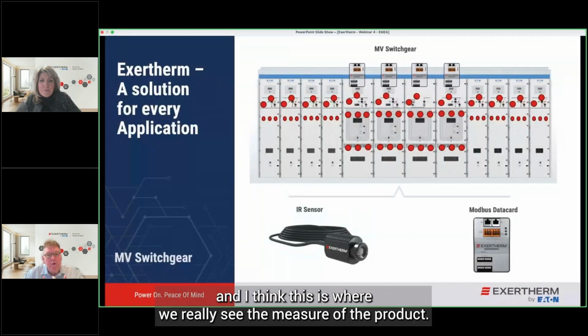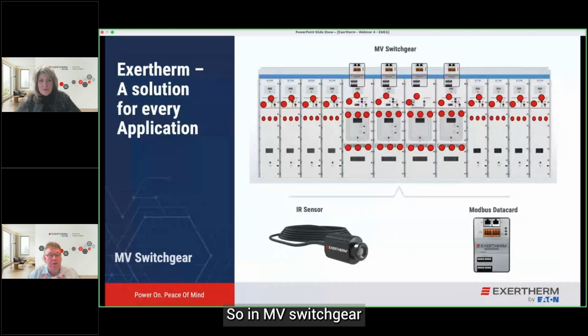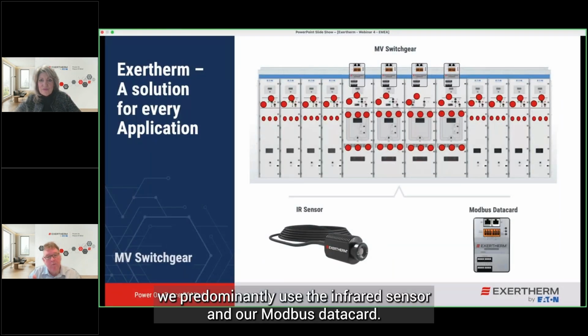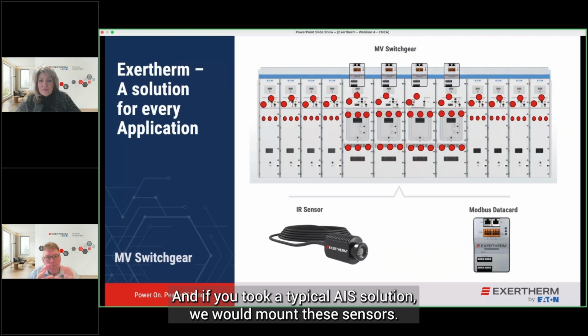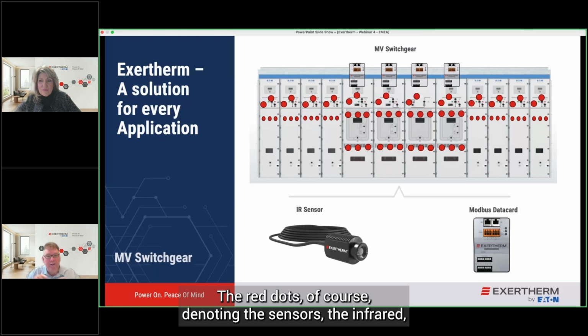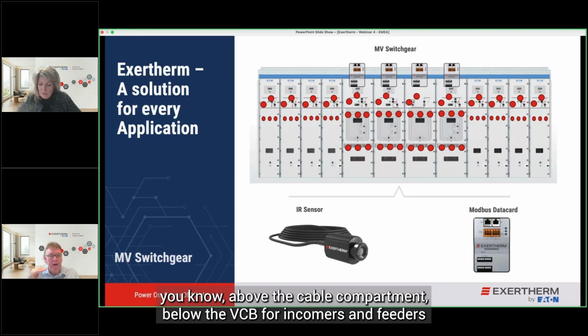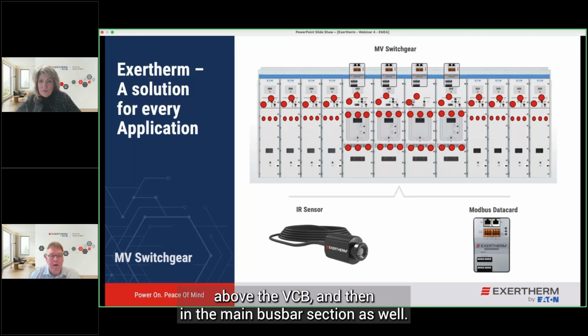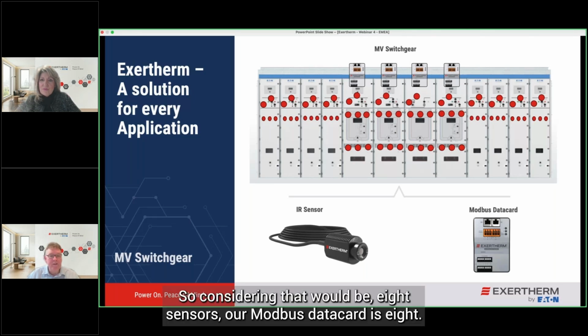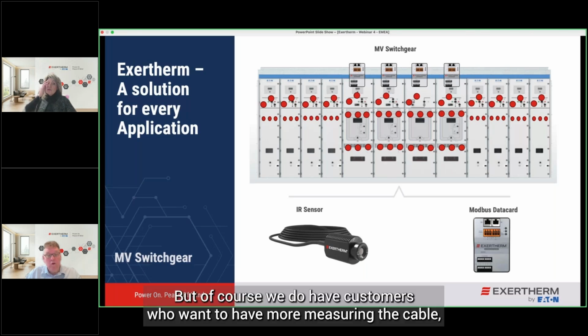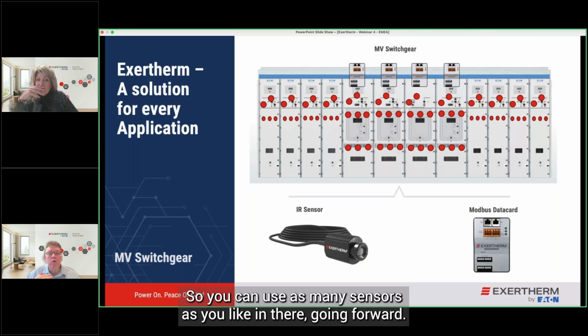So if we roll forward now into some of the applications, and I think this is where we really see the measure of the product. In MV switchgear, we predominantly use the infrared sensor and our Modbus data card. If you took a typical AIS solution, we would mount these sensors, the red dots denoting the infrared sensors, above the cable compartment below the VCB for incomers and feeders, above the VCB, and then in the main bus bar section as well. That would be 8 sensors, and our Modbus data card takes 8. But of course, we do have customers who want more measuring the cable compartment itself, so you can use as many sensors as you like in there going forward.